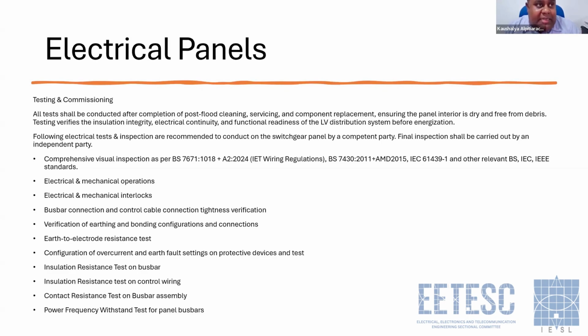Electrical and mechanical operations may be checked through a separate power supply, along with interlocks, bus bar connection, control cable connection, and tightness verification. Verification of earthing and bonding, configuration and connections, earth electrode resistance test, configuration of overcurrent and earth fault settings on protective devices, and test. All the tests will have to be carried out for long time, short time, and instantaneous, because you need to verify the solenoid operation and the trip unit operation.